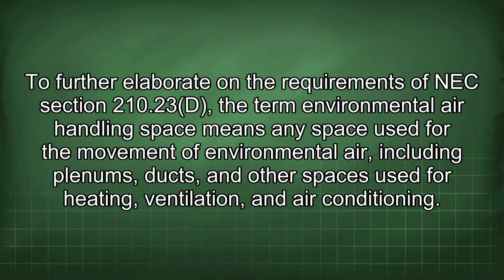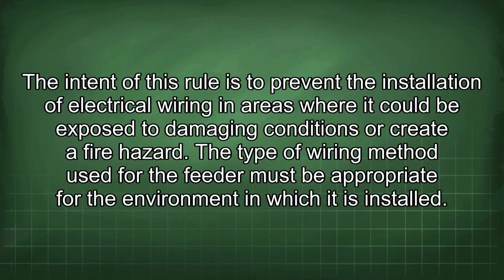To further elaborate on the requirements of NEC Section 210.23(d), the term environmental air handling space means any space used for the movement of environmental air, including plenums, ducts, and other spaces used for heating, ventilation, and air conditioning. The intent of this rule is to prevent the installation of electrical wiring in areas where it could be exposed to damaging conditions or create a fire hazard.